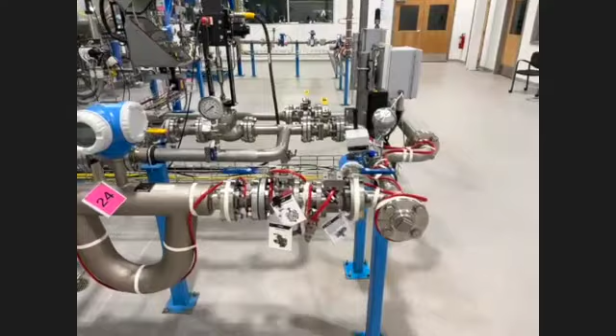I have a question, Ryan. Sure. Whenever you install heat trace, it's all nice when you don't have the insulation, but once it's buried in insulation and you have a device like you have there, you may have to service it. Is there a strategy of laying the heat trace down so it can be unwound off of the pipe, so it doesn't coil around the pipe, making it almost impossible to pull that one section loose so you can remove that device? Kind of loop it around, that way you can uncoil it off that device.